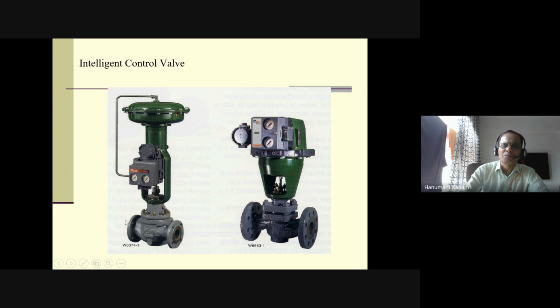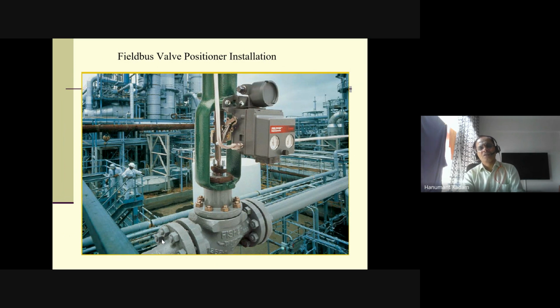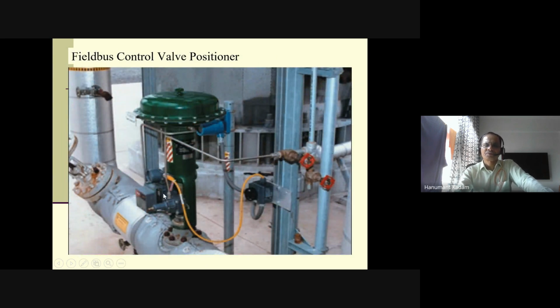This is a picture of an intelligent valve, meaning a smart positioner. This is not a pneumatic positioner; it is a fieldbus and HART positioner. You see, this is the picture. This is the positioner, and this is the control output. So fieldbus positioner, or if you see in the plant, this is a valve, and you see this positioner is installed here. There are two indicators which show the air supply and the control output. Above this, you can see the backside link is there. So this is a fieldbus valve positioner. On this valve, you can see the fieldbus connections through this termination box. This is a spur cable.